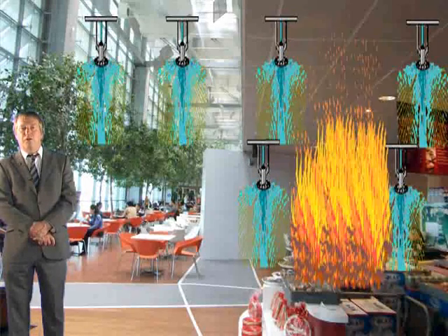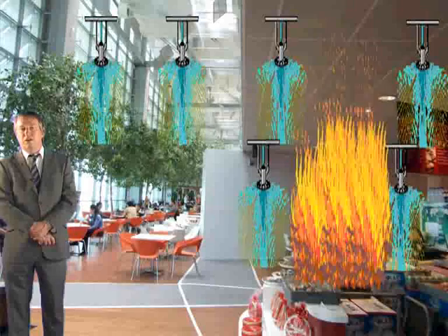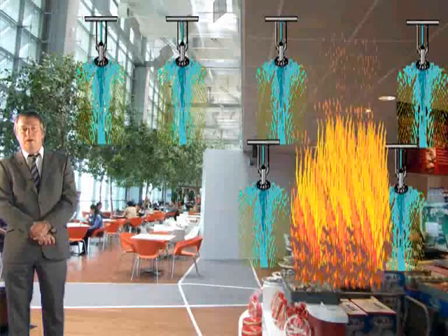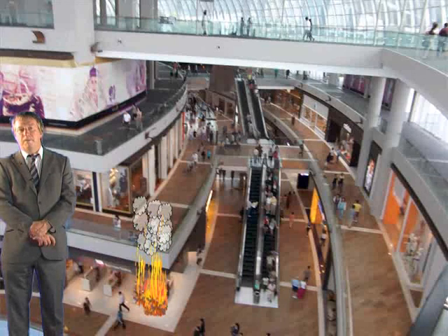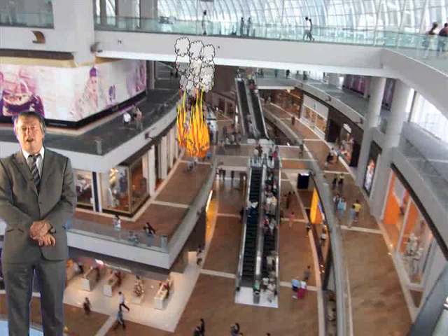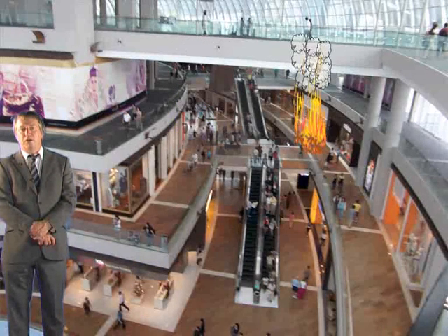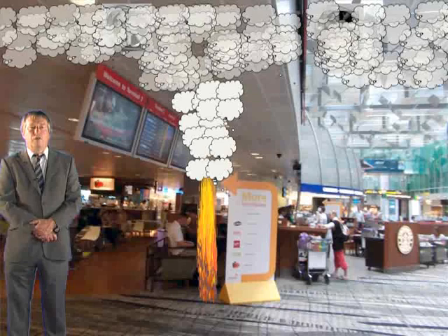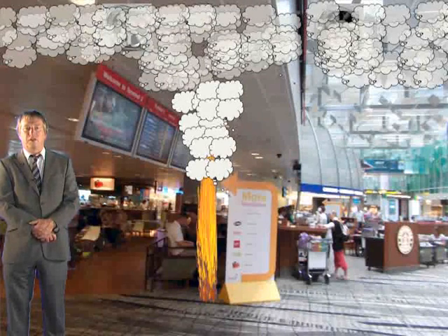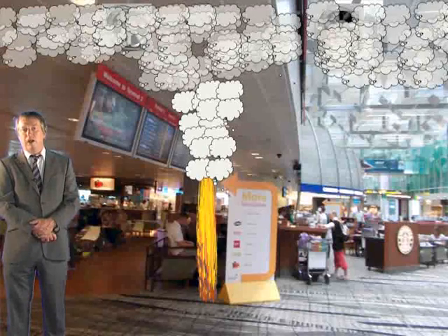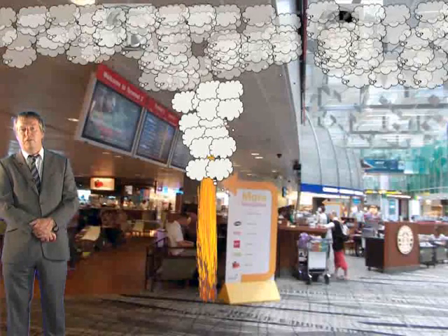This containment of fire is expected in about 95% of cases, and the confidence level of 95% is usually deemed sufficient. As mentioned earlier, there may be situations where you have to carry out a number of scenarios to identify which is the worst case. For example, in an airport atrium, you may have a few potential different fire sizes, and you may have to work them all out to determine the highest mass flow rate of smoke and the highest temperature of the smoke layer.